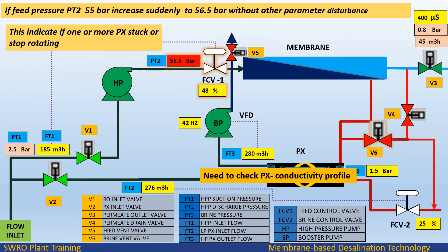During normal plant operation, if feed pressure PT2 at 55 bar increases suddenly to 56.5 bar — about 1.0 to 1.5 bar — without any other parameter disturbance, this indicates that one or more PX units are stuck or have stopped rotating.